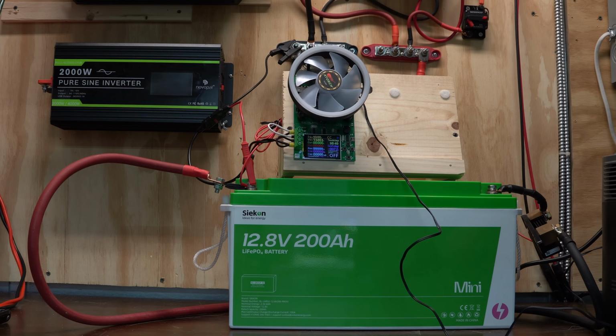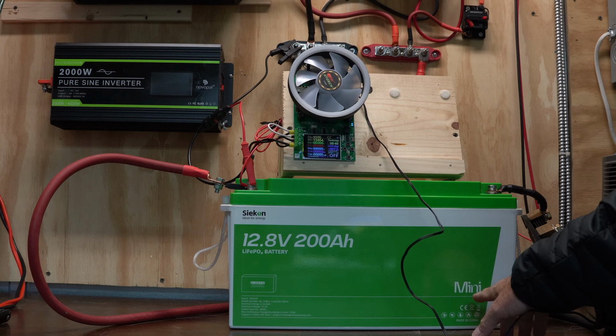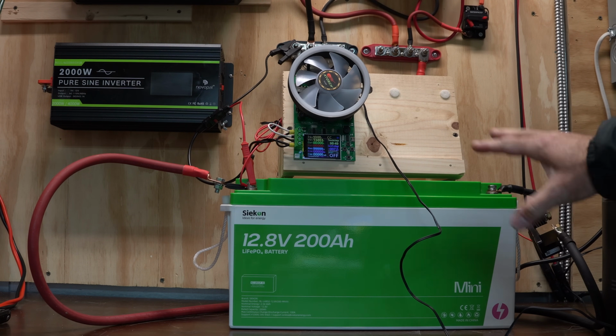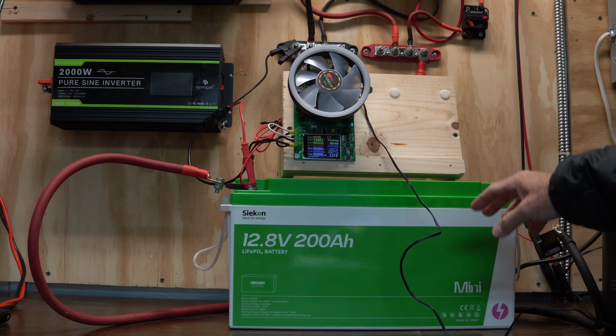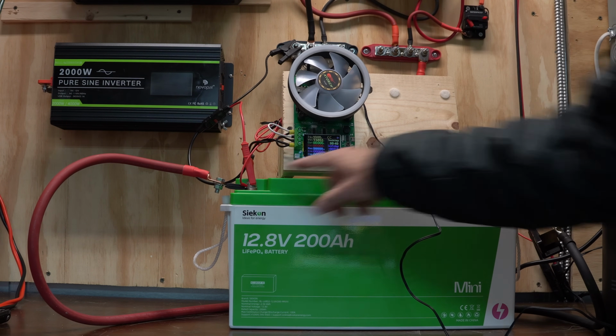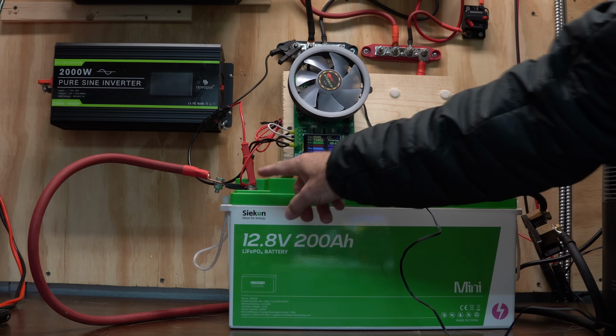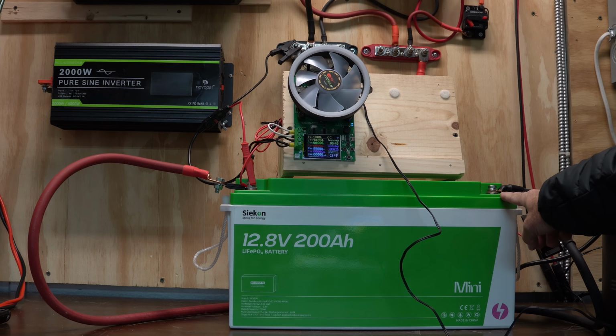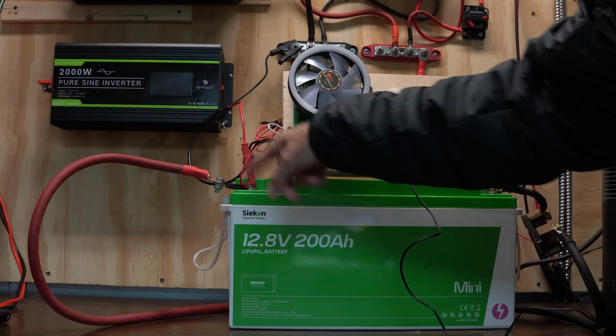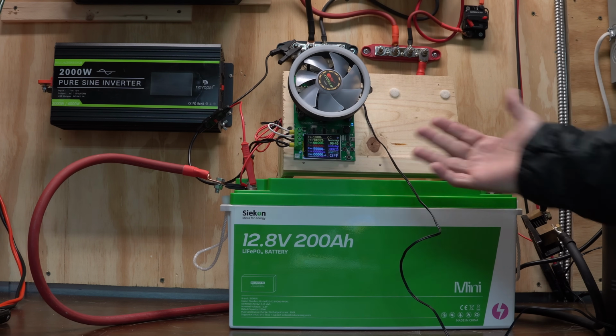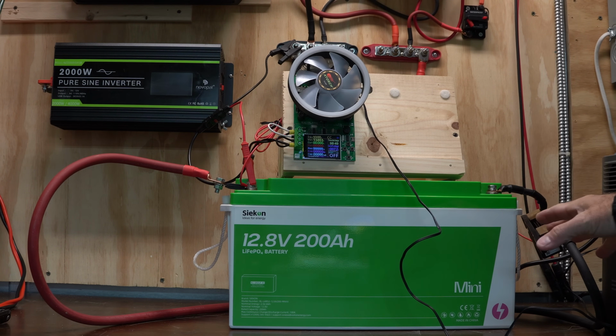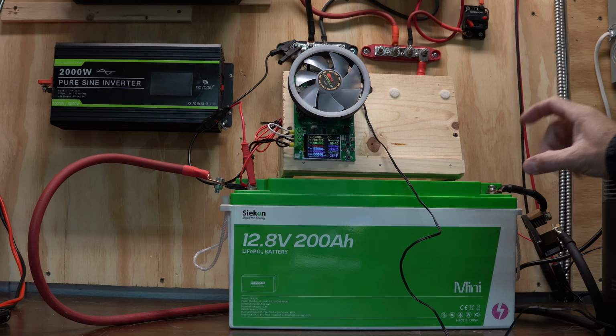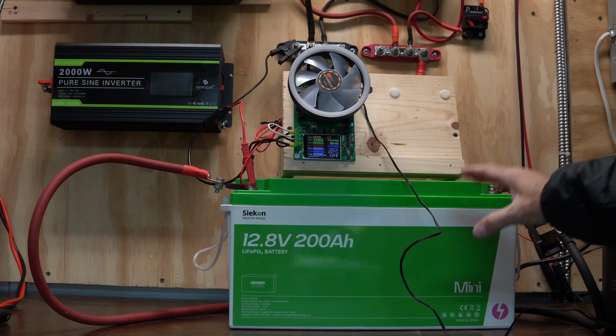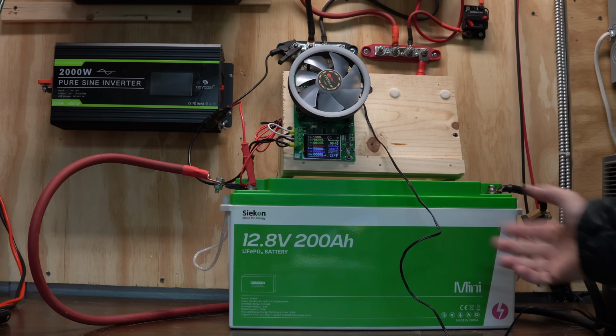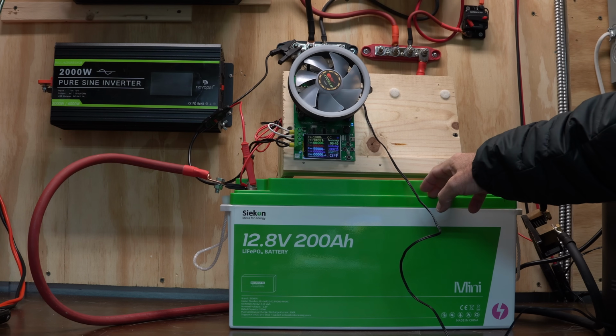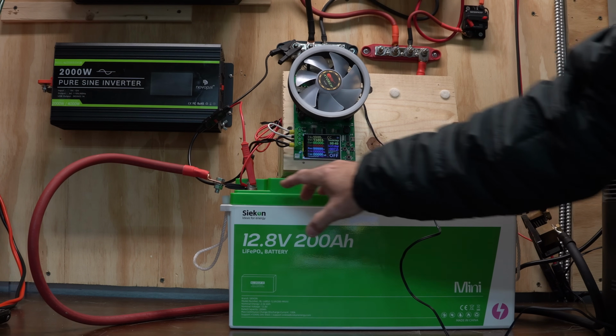All right, let's check the usable capacity on this 200 amp hour mini. At first glance it kind of looks like the other 200 amp hour classic, but if you notice, the terminals are spaced lengthways on top, much further apart, instead of all being on one end. The mini has a slightly smaller overall footprint than the classic 200 amp hour - not dramatically different, but a little smaller.